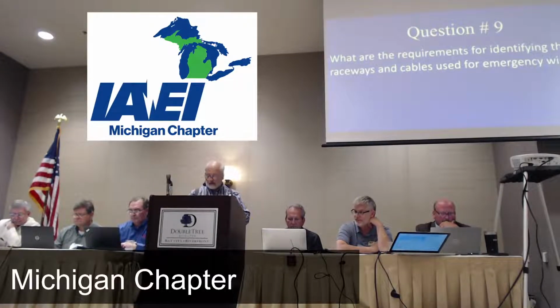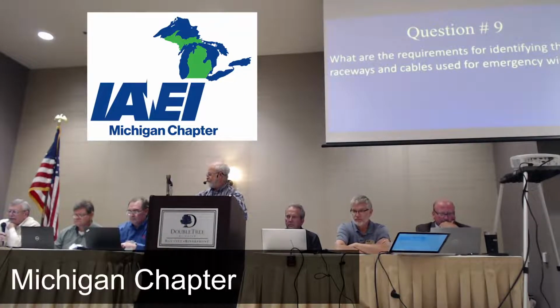Joe, what are the requirements for identifying the raceways and cables used for emergency wiring? So for this one, I referenced 700.10(A). 700, of course, is emergency systems, and 10(A) talks about identification. And it reads, emergency circuits shall be permanently marked so they will be readily identified as a component of an emergency circuit or system by the following methods. I'm going to stop right there, because I've never read this really closely until I got to this question. In my opinion, I think it should say by one of the following methods, because if you read number 1 and number 2, it kind of implies that you can do one or the other. But it doesn't say that in the charging sentence.